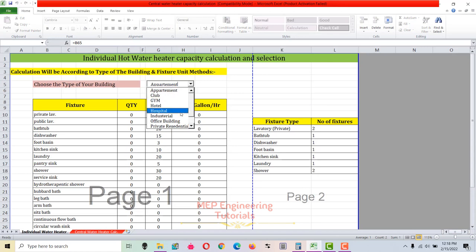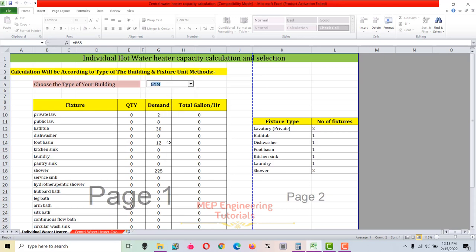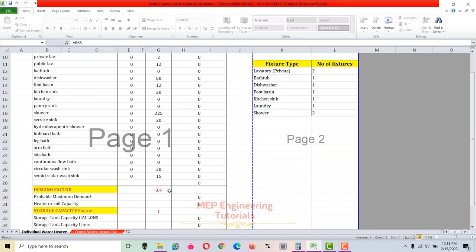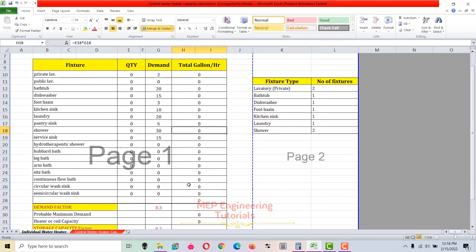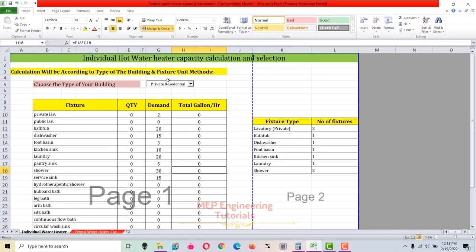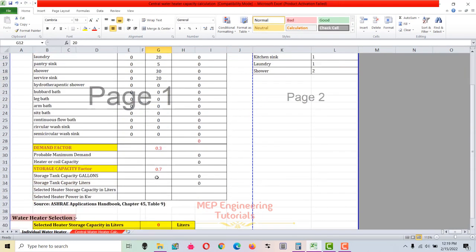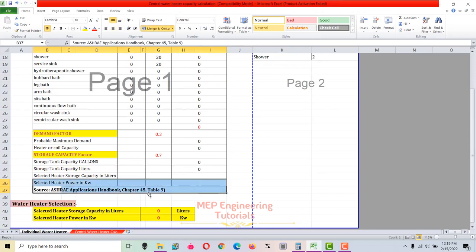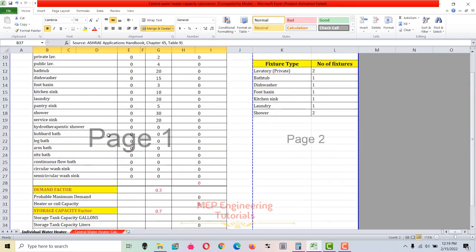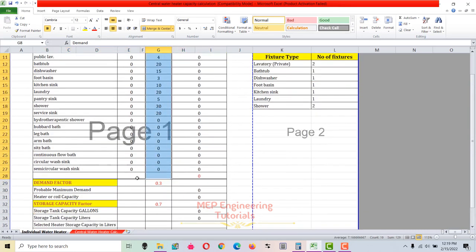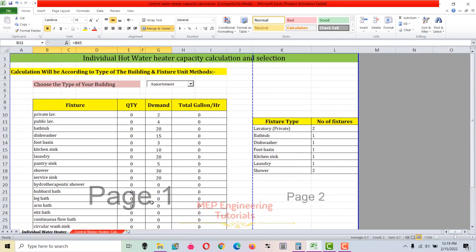There are several types of buildings available: apartment, club, gym, hotel, hospital, industrial, office building, private residential, and many more. If you select gym, the demand, demand factor, and storage capacity all change; same if you select industrial or private residential. Let's select apartment. This table is extracted from the ASHRAE Application Handbook, Chapter 45, Table 9.